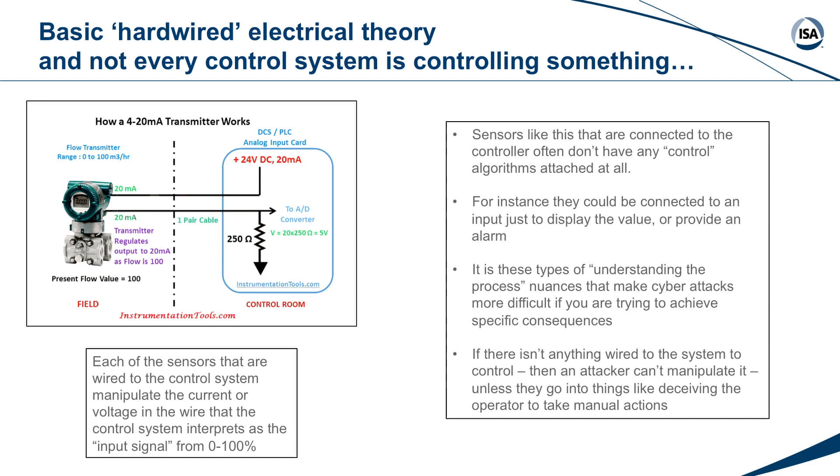You can also borrow some of the power in that 4 milliamps to power your instrument. So most of these instruments don't have separate power supplies — they glean the power off of that 4 milliamp signal going around in the circle. So 4 milliamps is your 0, 20 is your 100%. And if you're a control engineer, you have 250 ohm resistors falling out of your pocket everywhere, because if you run 20 milliamps through 250 ohms, you get 5 volts. So you get that voltage drop across that resistor that becomes your signal into your industrial control system.